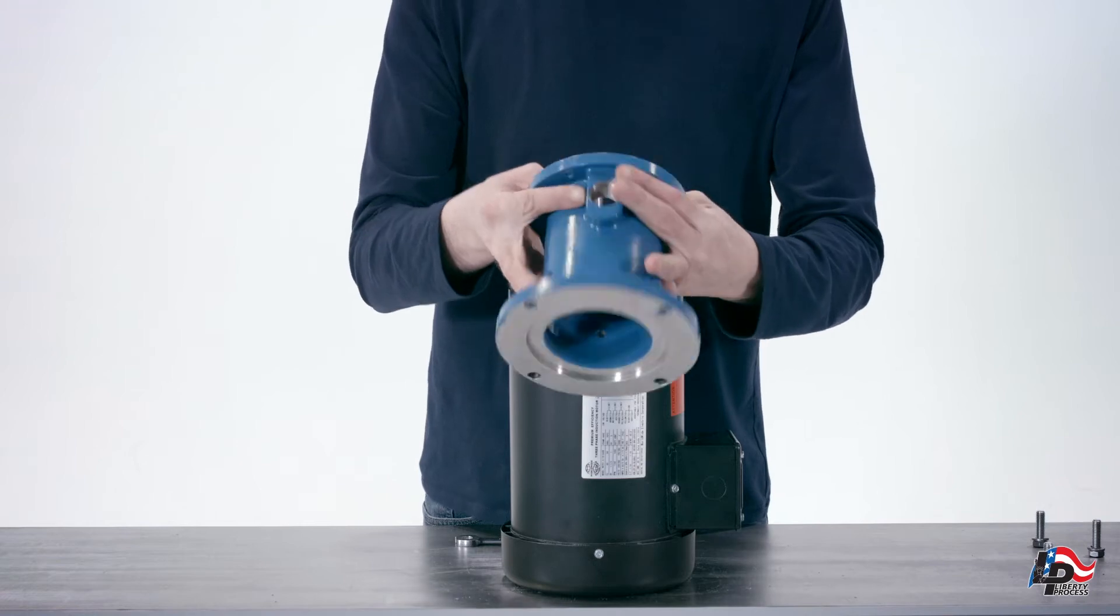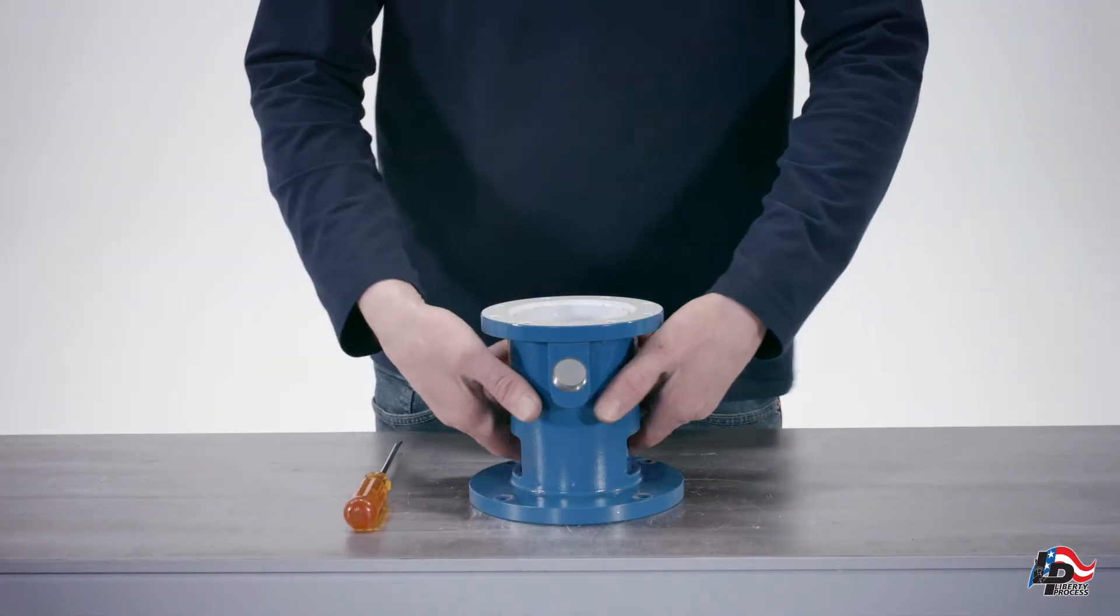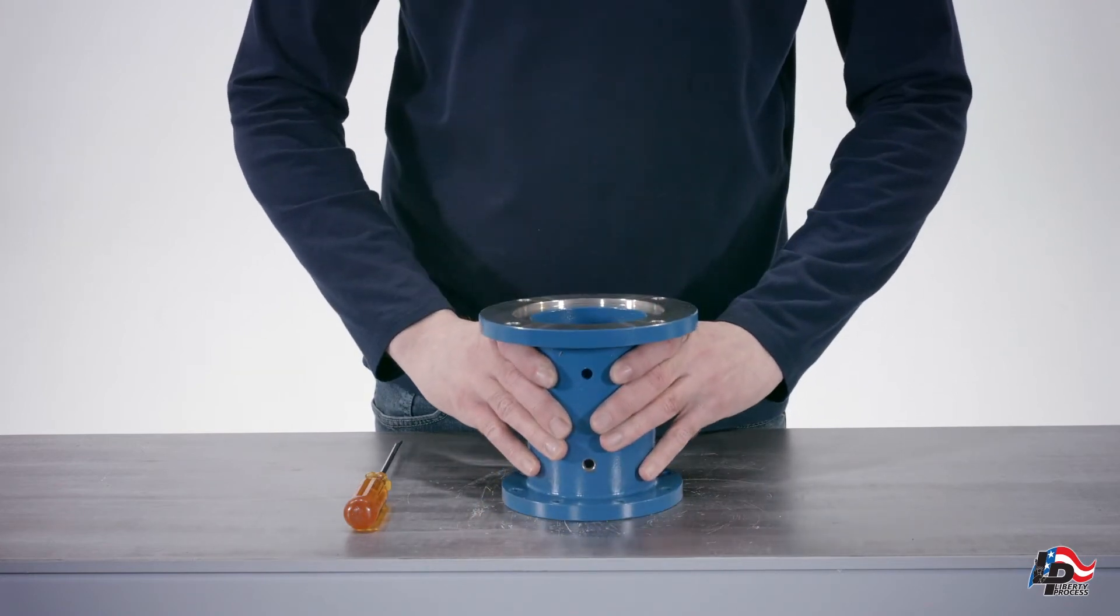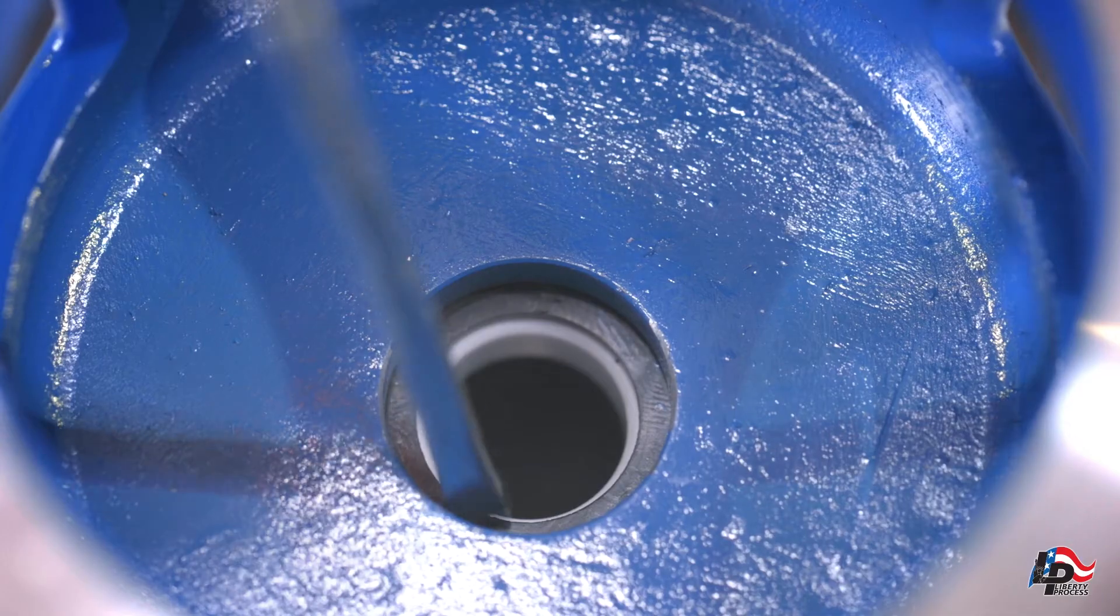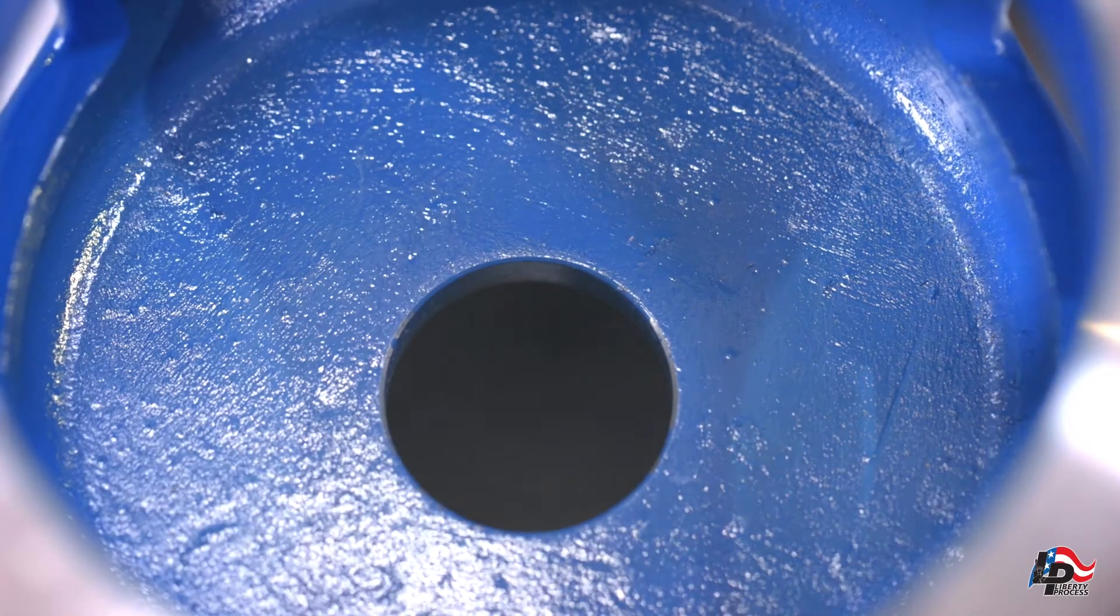To remove the stationary face of the mechanical seal from the pump discharge casing, turn the pump discharge casing over. Using your fingers, press out the stationary face of the mechanical seal. If it remains stuck, use a flat-bladed screwdriver to gently pry it loose.